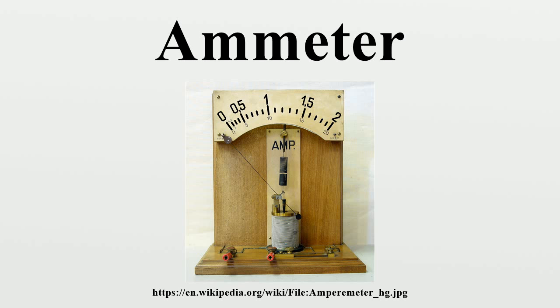Since the ammeter shunt has a very low resistance, mistakenly wiring the ammeter in parallel with a voltage source will cause a short circuit, at best blowing a fuse, possibly damaging the instrument and wiring, and exposing an observer to injury. In AC circuits, a current transformer converts the magnetic field around a conductor into a small AC current, typically either 1A or 5A at full rated current, that can be easily read by a meter. In a similar way, accurate AC, DC non-contact ammeters have been constructed using Hall effect magnetic field sensors. A portable handheld clamp-on ammeter is a common tool for maintenance of industrial and commercial electrical equipment, which is temporarily clipped over a wire to measure current.